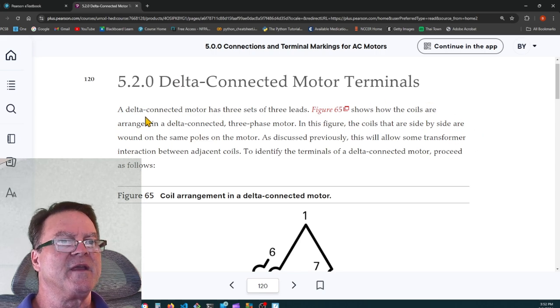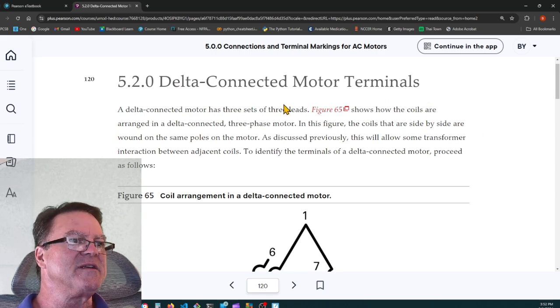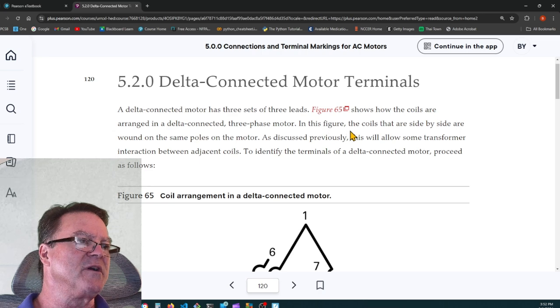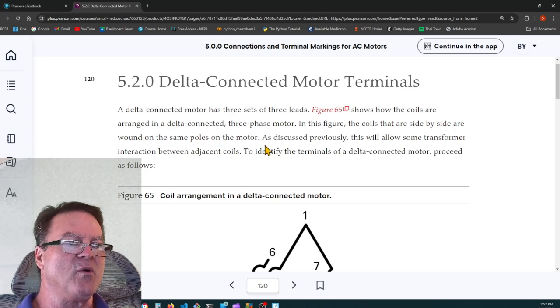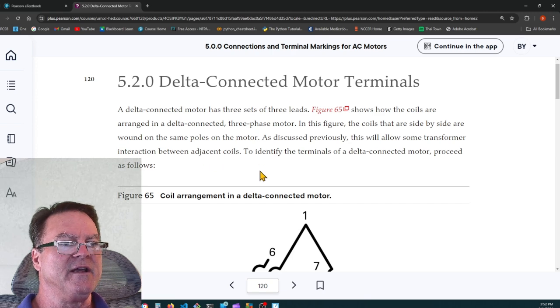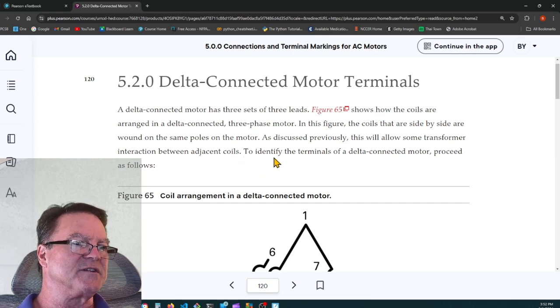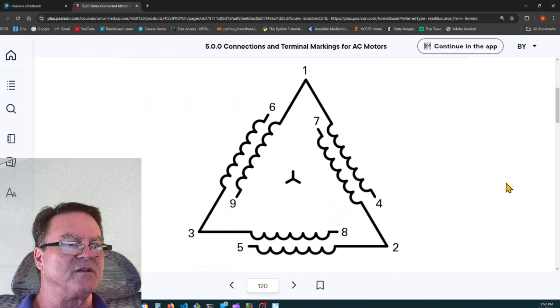Delta-connected motor terminals. A delta-connected motor has three sets of three leads. Figure 65 shows how the coils are arranged in a delta-connected three-phase motor. In this figure, the coils that are side by side are wound on the same poles of the motor. As discussed previously, this will allow some transformer interaction between the adjacent coils. To identify the terminals of the delta-connected motor, proceed as follows.